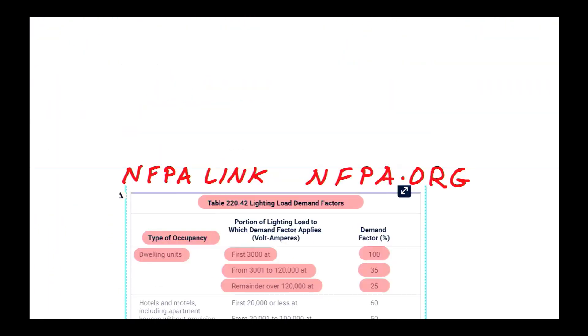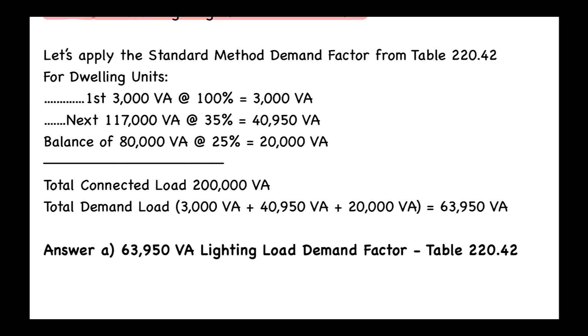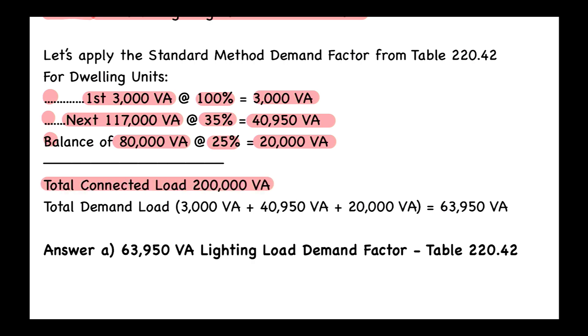Let's apply the standard method demand factor from Table 220.42 for dwelling units. We take the first 3,000 VA at 100%, giving us 3,000 VA. Then we take the next 117,000 VA at 35%, giving us 40,950 VA. Then we take the balance of 80,000 VA at 25%, giving us 20,000 VA. Notice that 3,000 + 117,000 + 80,000 equals our total connected load of 200,000 VA.